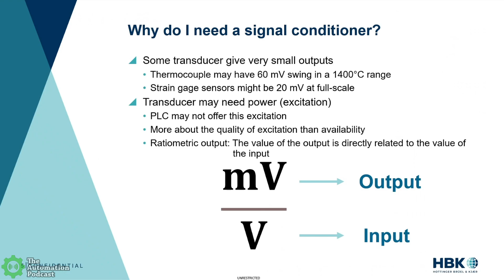Yeah, certainly. And the beauty of something like a millivolt per volt, quote unquote unit, is that it's the same regardless of your excitation. So if you have a signal conditioner that gives 1 volt excitation or 2.5 volt excitation or 5 volt excitation, because your transducer is being described in millivolts per volt, it's always normalized. So regardless of the magnitude of excitation, you're always getting the same ratiometric output, which makes it pretty convenient. It means you don't have to always ask what the excitation voltage was and do that mental math. Go ahead.